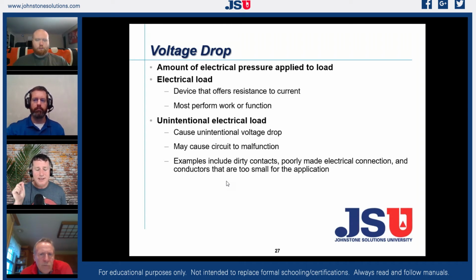Well, what happens if I build up resistance on my contact points? If I change my conductor to a load, you will create heat and eliminate electron flow. So you might drop the voltage to the compressor or the capacitor or whatever. That's the danger of letting the contactor get pitted.